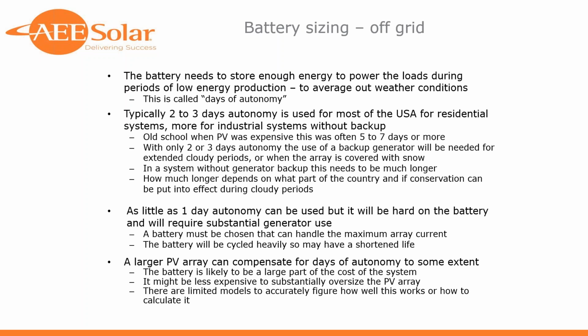For those trying to do without a backup generator, it certainly doesn't hurt to have more days of autonomy on your battery bank. It just costs more. It also depends on what part of the country you're in. In some parts of the country you may not get that many cloudy days, and you may be able to get by with fewer batteries. Certainly where I am here in Olympia, Washington, if we were to try to do a system without any backup power, we would be looking at 28 days of battery autonomy or something like that. So that doesn't work so well up here.